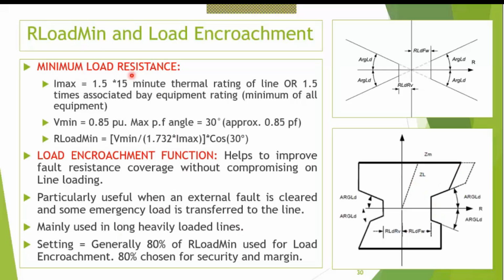And generally, the minimum load resistance is 1.5 times the 15-minute thermal rating of the line, or the associated bay equipment's minimum rating. Suppose I have a CT which is 800 ampere. My line is very powerful, so my CT can burst if I allow it to carry that for 15 minutes. So the lowest equipment rating ultimately decides the thermal rating of the line.